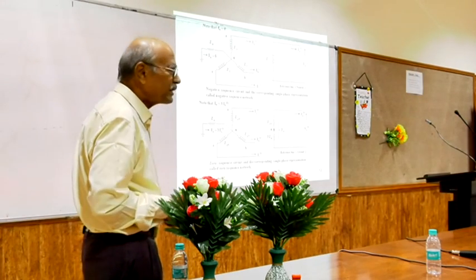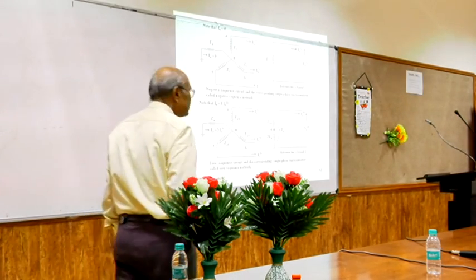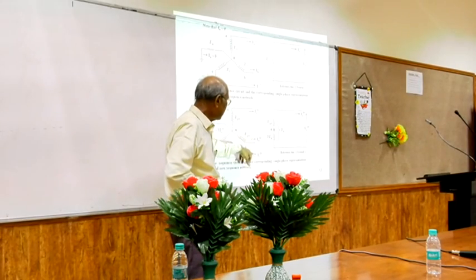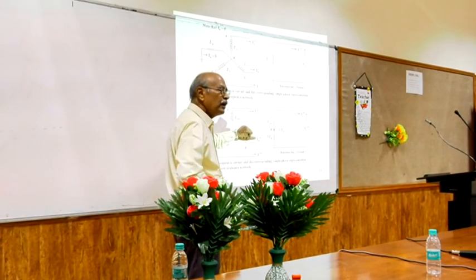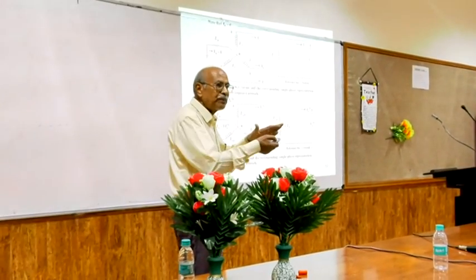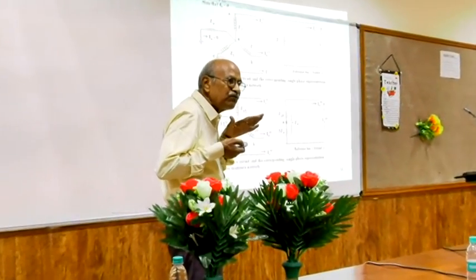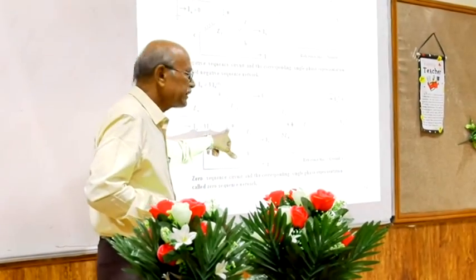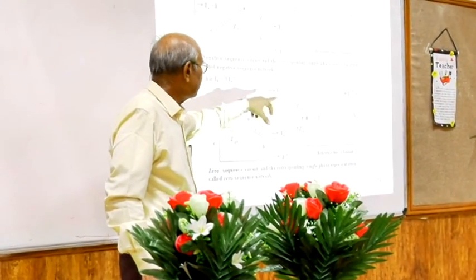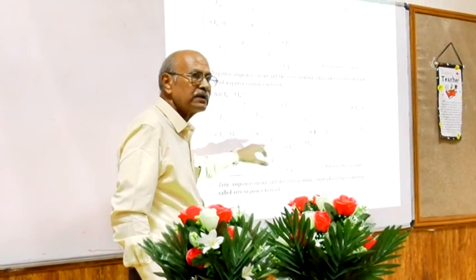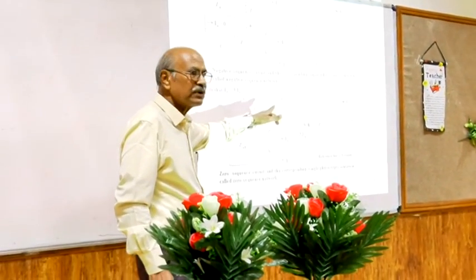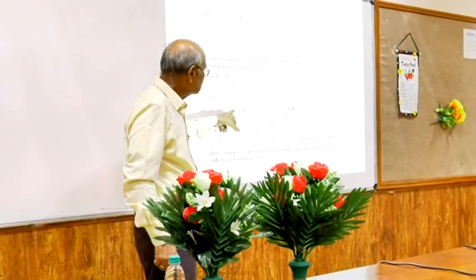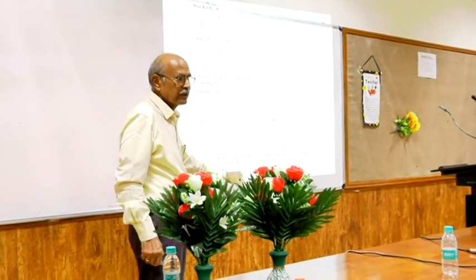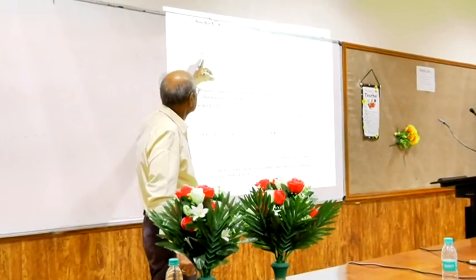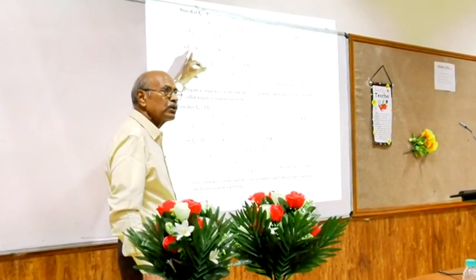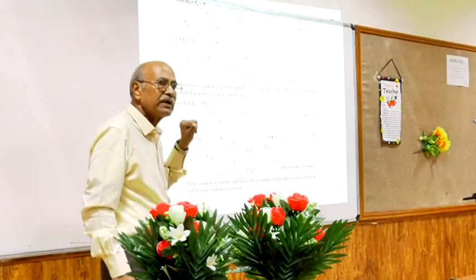Then for the zero sequence network, it is slightly different. Zero sequence currents are IA0, IB0, IC0. If you look at the zero sequence component, they are equal and in the same phase. So if I apply Kirchhoff's current law at this point, the outgoing currents IA0, IB0, IC0 are all equal, so the total is 3 times IA0. So previously there was no current in the neutral, but now I have current at 3 times IA0.